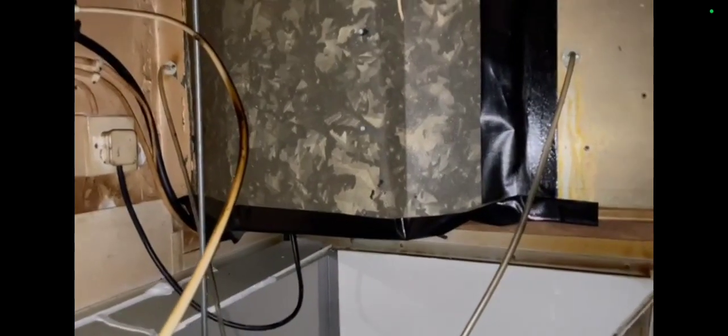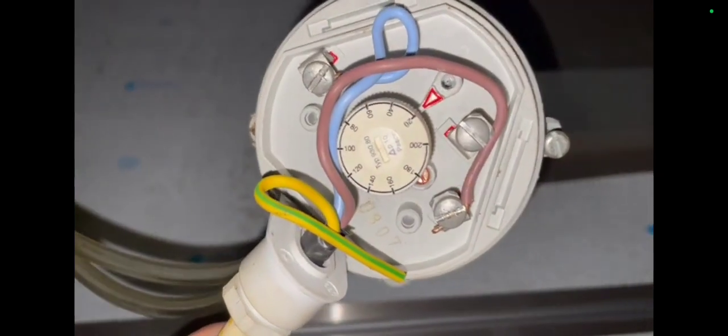The hood's recently been changed, so to get over to this unit it's going to take some agility. So I've got two extractors, one's working, one's not working, and it's due to the air pressure switch not making. So I managed to get this air pressure switch down, the one that is not making. There it is, it's at 20 pascals.